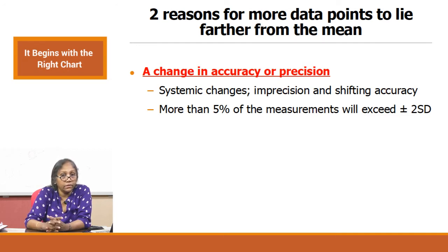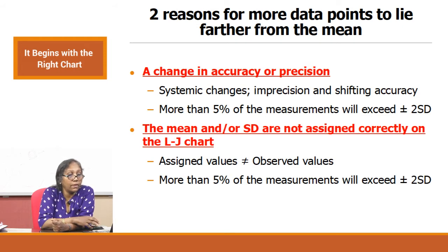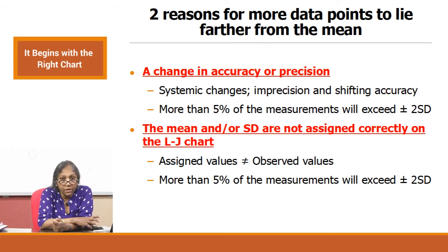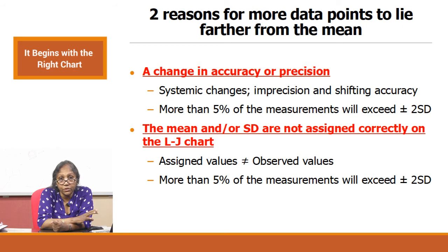If it goes beyond plus or minus 2 SD and you see more than 5 percent, what could be the reasons? Apart from a problem in your analytical system, the problem could be that the mean and/or SD are not assigned correctly on the LJ chart. This is one problem seen in many labs — the laboratory assigns values based on the QC package insert.